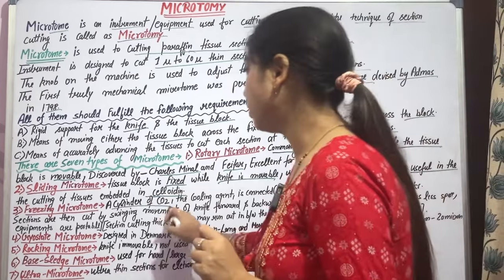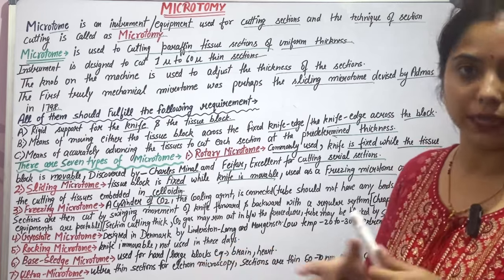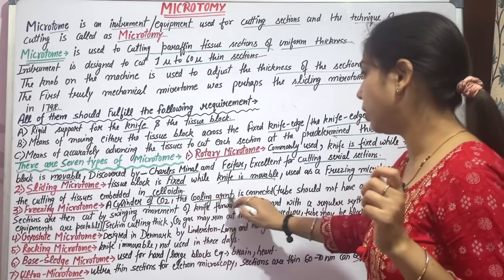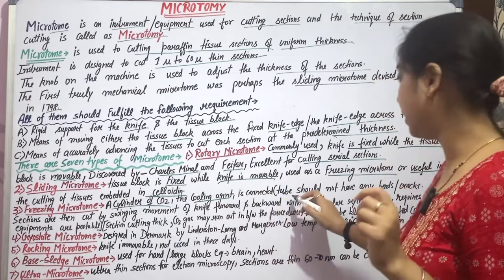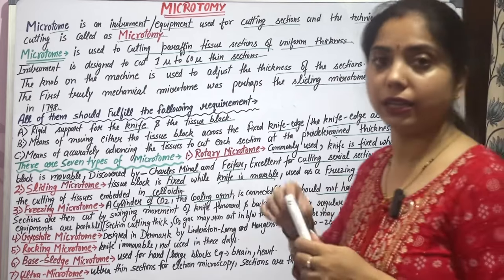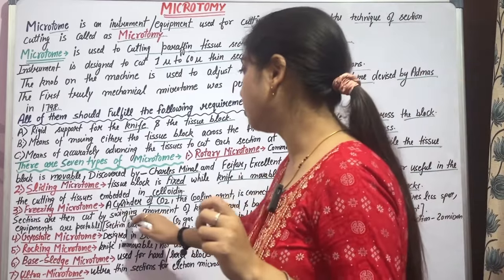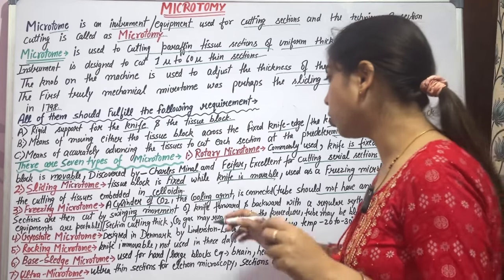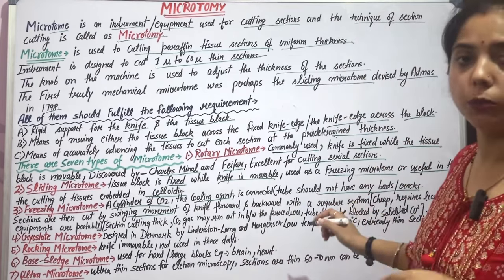The freezing microtome uses CO2 gas from a cylinder connected to the microtome. The CO2 acts as a cooling agent and is connected via a tube. The tube should not have any bends or cracks. Sections are cut by a swinging forward and backward movement of the knife with a regular rhythm.